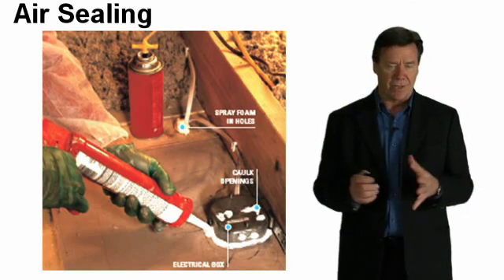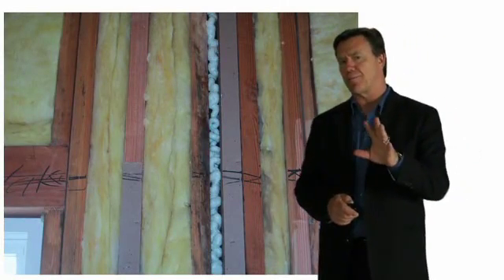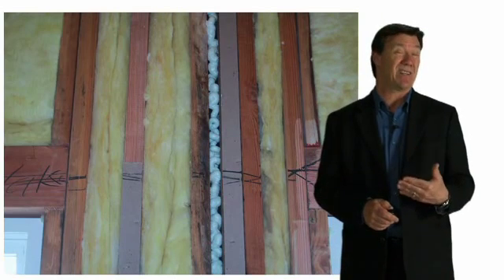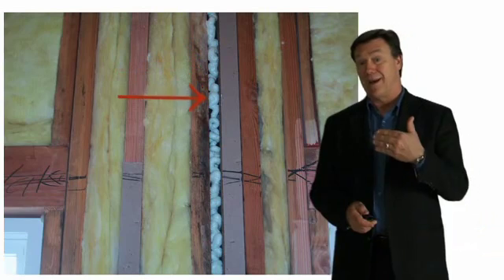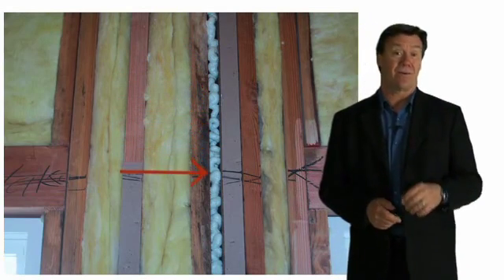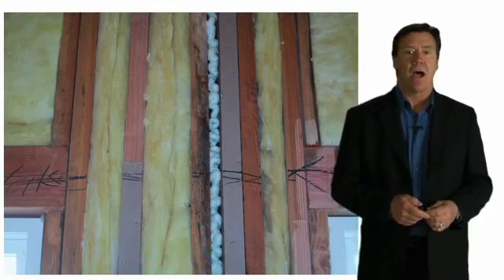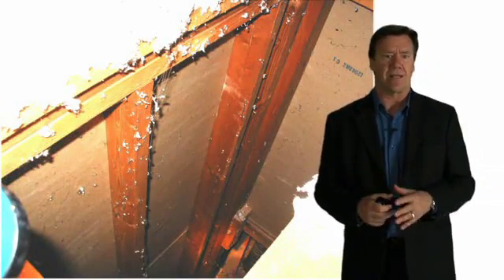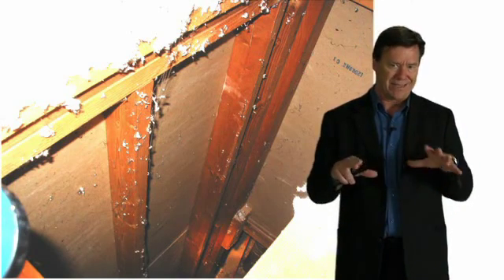It's important during the inspection process to make sure that air sealing is done adequately. It doesn't do any good to do a half job — having foam in an opening but not actually sealing the leak. Also, any drop ceilings or penetrations in the attic need to be boarded and sealed.